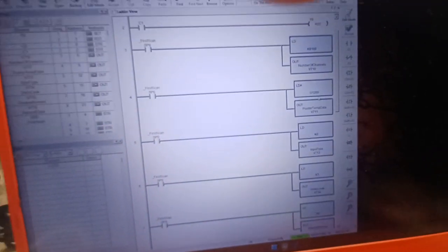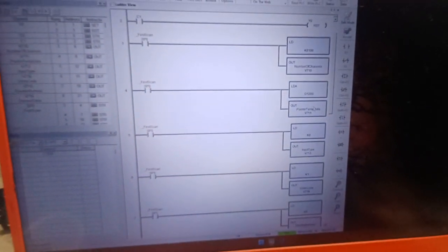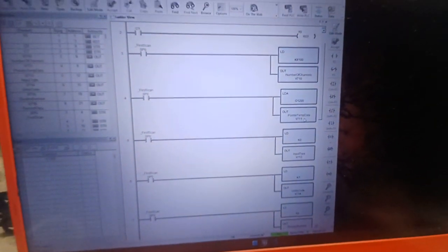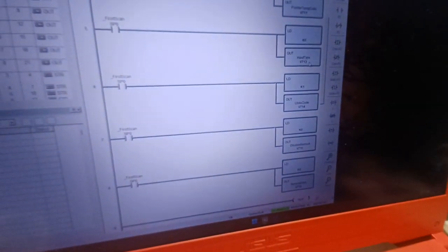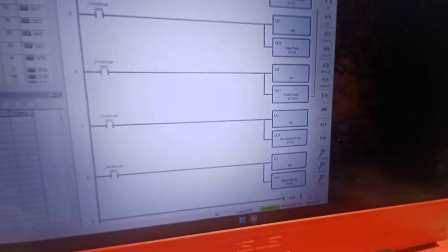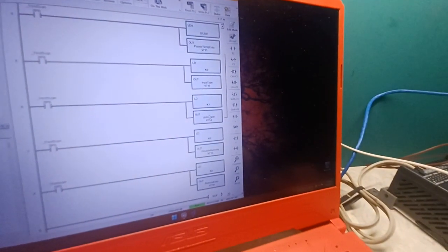Then the actual address location of the value is going to be obtained from the thermocouples. Then the input type, which is type K thermocouple, and then centigrade, Celsius, those are the units with a sign, so you can go negative too, I forgot what the lowest setting is for a type K thermocouple.